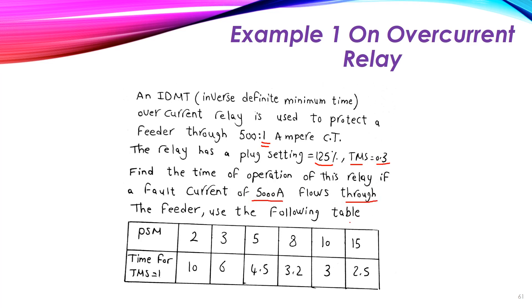We use the following table to find the operating time. The table gives the plug setting multiplier (PSM) values of 2, 3, 5, 8 — meaning two times, three times, five times the pickup current, and so on — with corresponding times at TMS equal to 1. At PSM=8, for example, the time is 3.2 seconds. Remember the table is for TMS equal to 1, but the required TMS is 0.3.